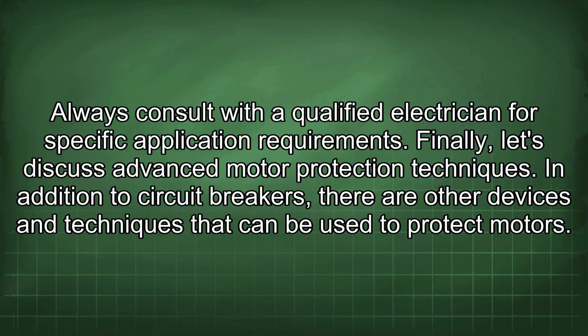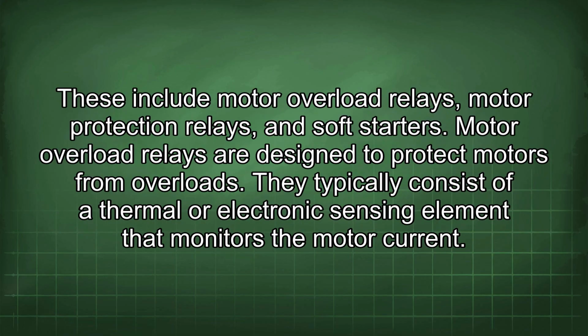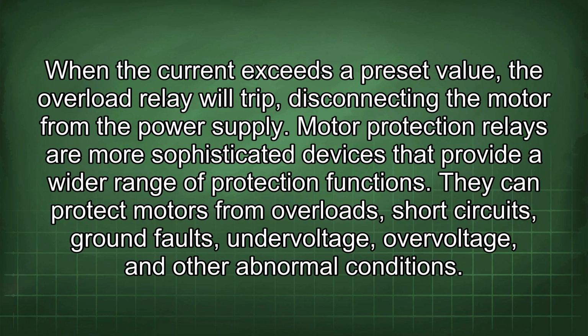Finally, let's discuss advanced motor protection techniques. In addition to circuit breakers, there are other devices and techniques that can be used to protect motors. These include motor overload relays, motor protection relays, and soft starters. Motor overload relays are designed to protect motors from overloads. They typically consist of a thermal or electronic sensing element that monitors the motor current. When the current exceeds a preset value, the overload relay will trip, disconnecting the motor from the power supply.